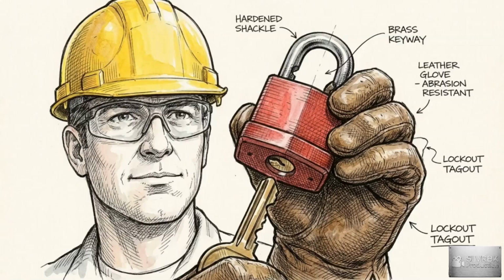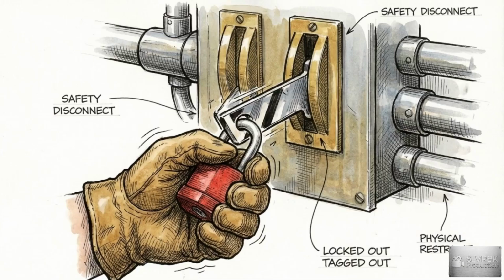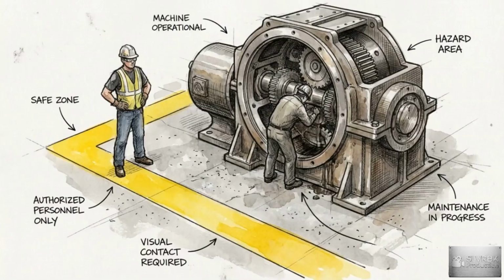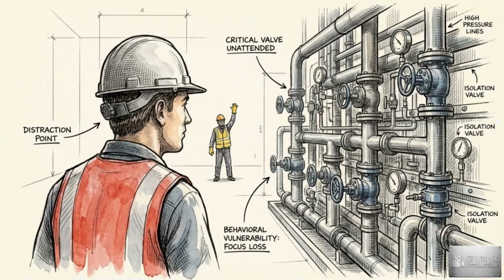The individual uniquely trained and responsible for isolating the energy and applying the locks or tags is the authorized employee. Once applied, the authorized employee maintains exclusive control. The physical lock protects them regardless of what anyone else on the floor does. The second category is the affected employee. This is typically the machine operator whose job requires them to be in the area, but who does not perform the actual maintenance. If a facility relies on tagout instead of lockout, an affected employee poses an extreme risk.